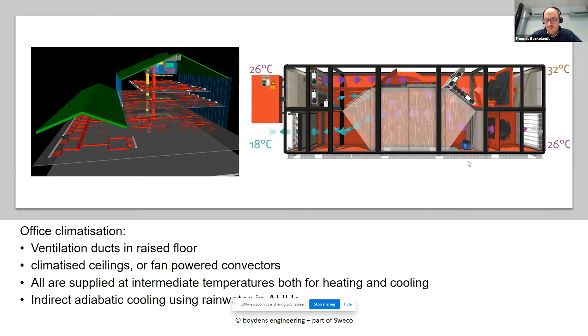What we added as well is, in the air handling unit, we use indirect adiabatic cooling, which sprays water into the foul airstream, cooling it down, and then this cold can be used in the fresh air stream to provide additional cold.